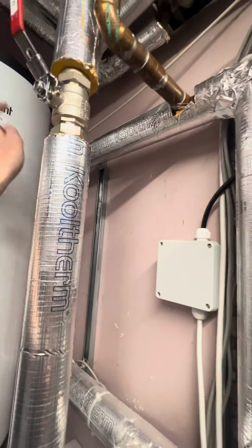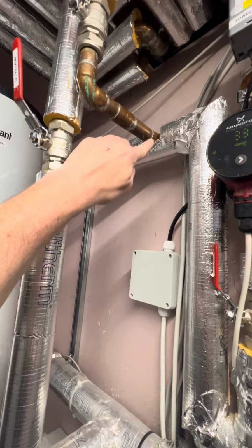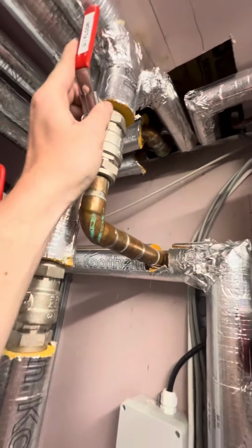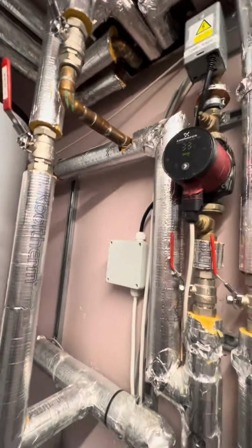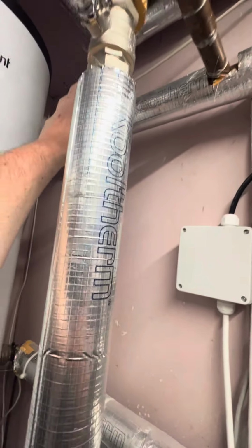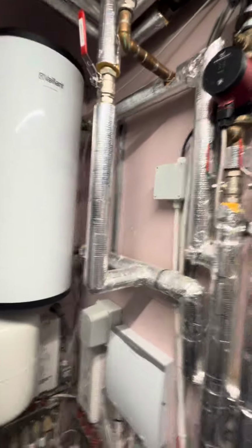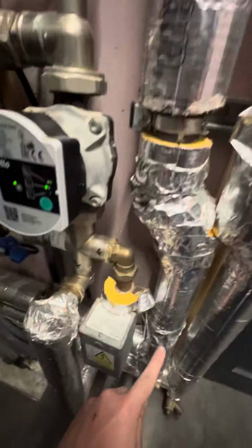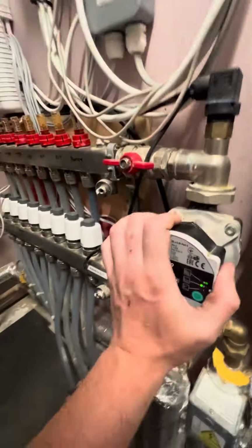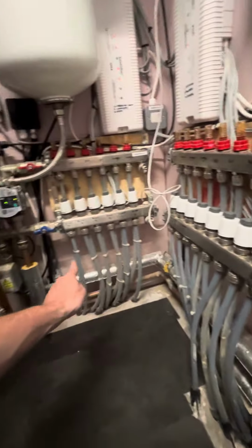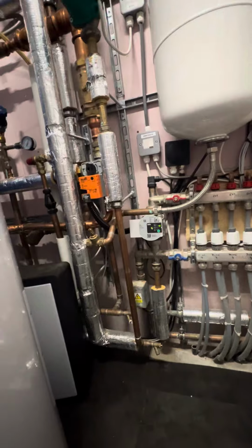On the secondary side, we come off here, and then because we've got hydraulic separation, we need another pump. So one pump we have on the top floor for the underfloor heating manifold up there, which I don't like, having the pumps all dotted around. I'd prefer to have, if they are required, additional pumps just here after the hydraulic separation. Anyway, we carry on down here and we tee off up here, and we have another pump just for our towel rail circuit. Or we come down here and we have another pump for this underfloor manifold, and we come along here and we have another pump just for that underfloor manifold there.